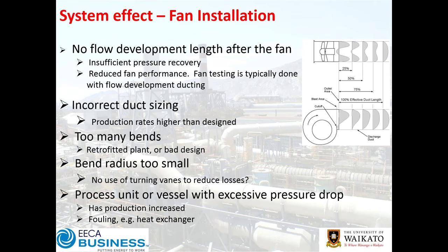Looking at the velocity profile right at the outlet of a fan, it's not uncommon on some fans to have a 10-to-1 ratio — perhaps 40–50 metres per second at the top and 4 or 5 at the bottom, and in some cases slightly negative flow. If you don't allow good flow development after the fan, that dynamic head in the high velocity air doesn't get fully recovered — it gets wasted, and the fan performance is somewhat less than expected.